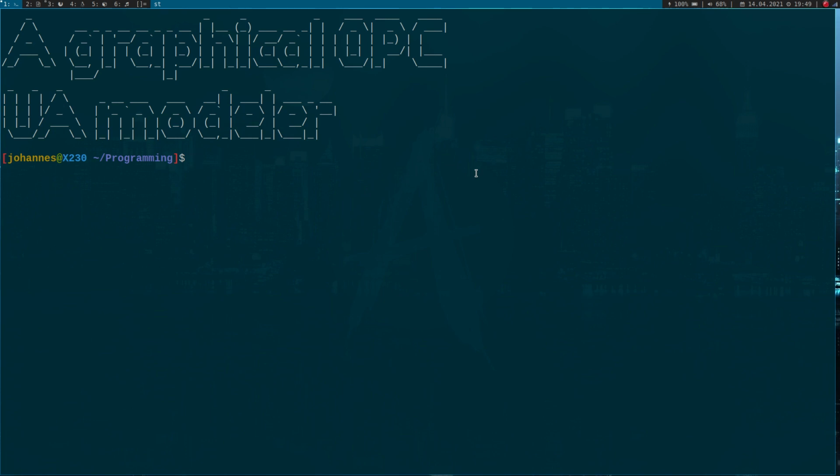And the second advantage is, as an output of the OPC UA modeler, you won't get source code. No, you will get a standardized XML file which describes how your server looks like. And with this XML file, you can set up your server on different platforms using different OPC UA implementations. For example, you can import it with Python OPC UA, or you can take your XML file and generate the source code for an open62541 server out of it.